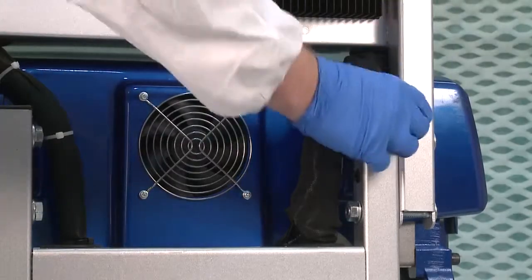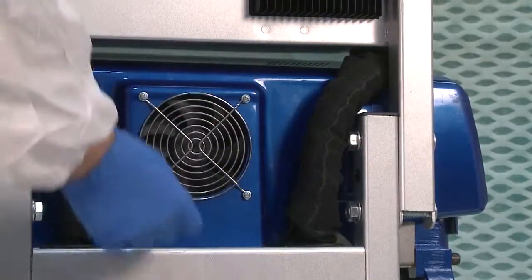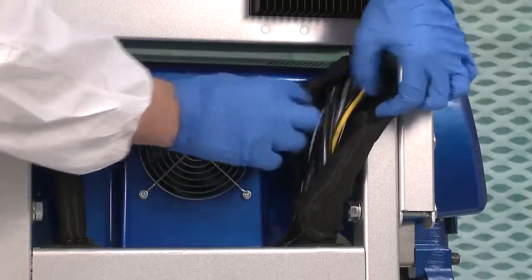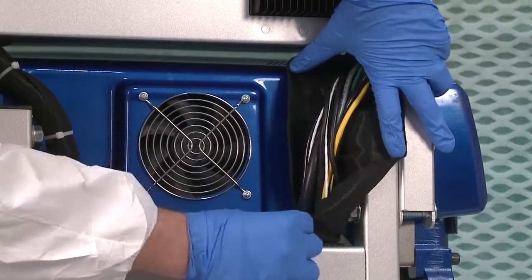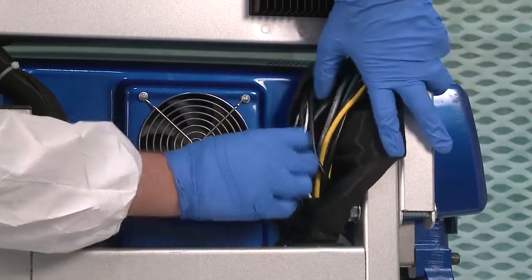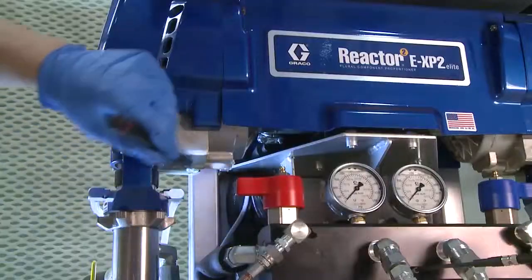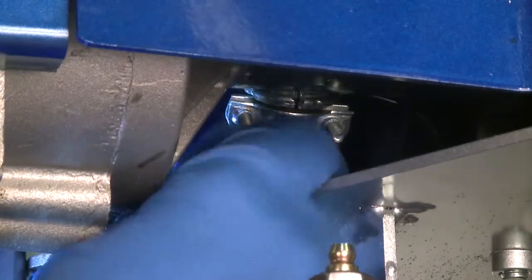Remove all cable ties and pull back protective covering so that the wire can be fully inspected. When finished, be sure to re-secure wiring and protective covering with new cable ties. Finally, verify cable is not damaged at strain relief on motor case.